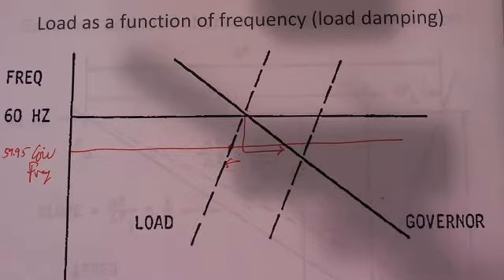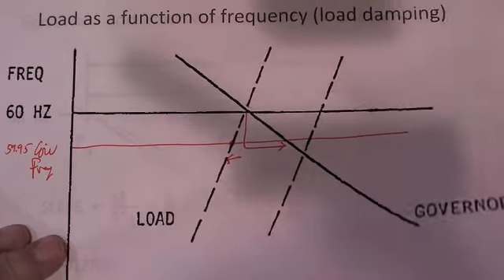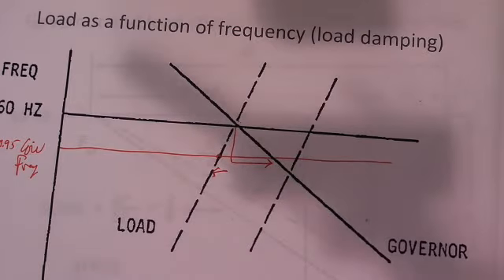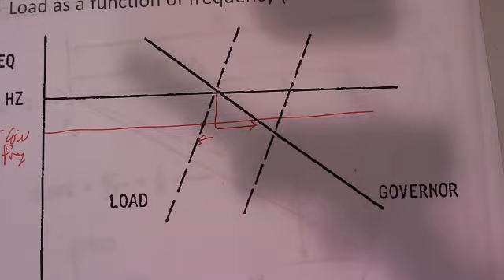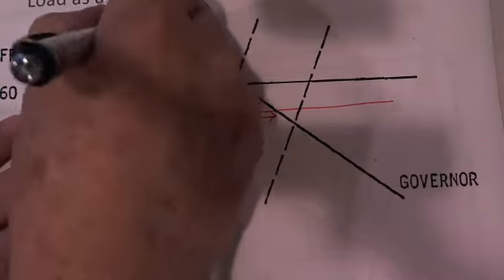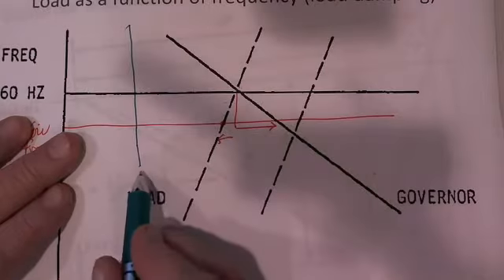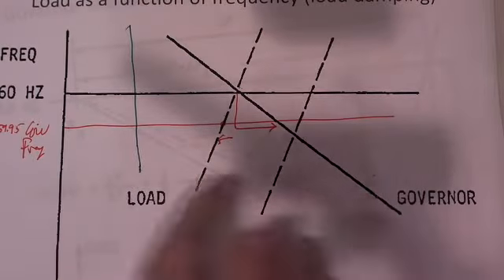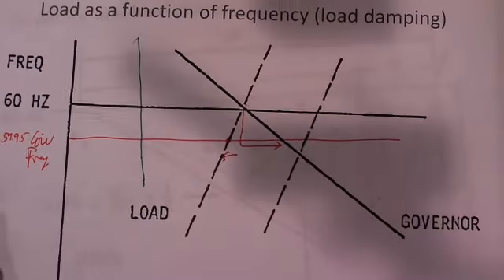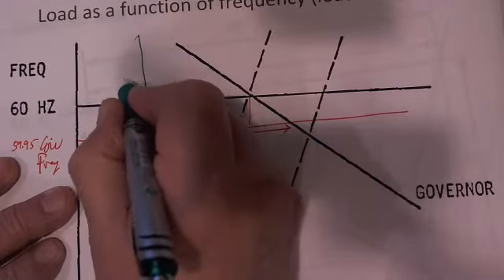Incidentally, one of the things about producing power from something like a large solar array: you turn it on, and you have an inverter there that converts DC to AC. But if the frequency of the system changes, that's not going to change the power output. So a solar array, a PV, would have a characteristic like this. Do anything you want with the frequency, the power output is the same. That's whatever amount of sunlight is hitting the solar array. And I didn't draw that perfectly. I meant to draw this vertically, so this is supposed to be 90 degrees here.